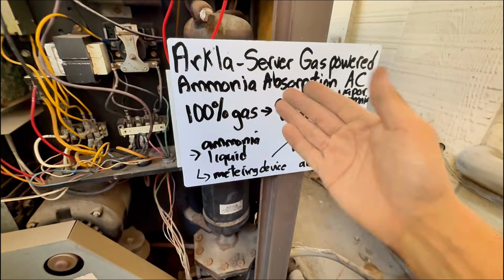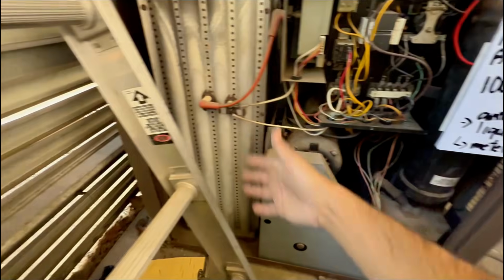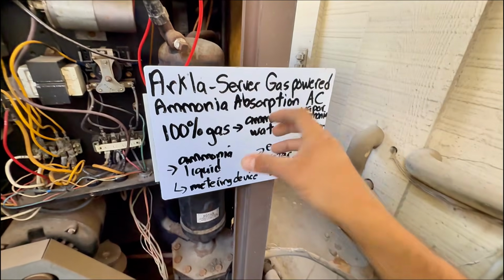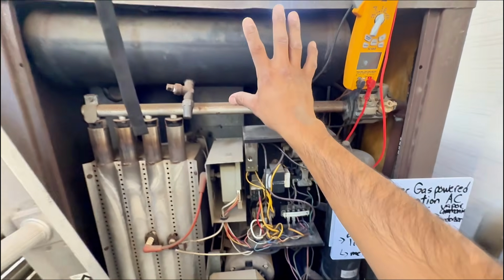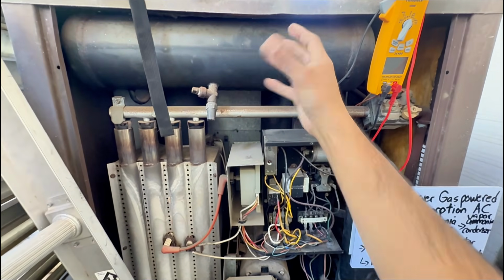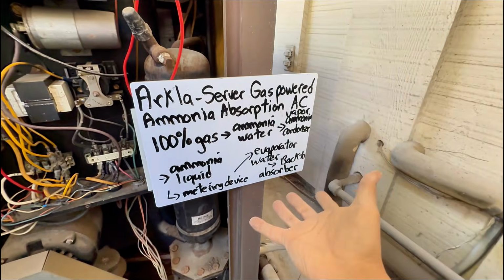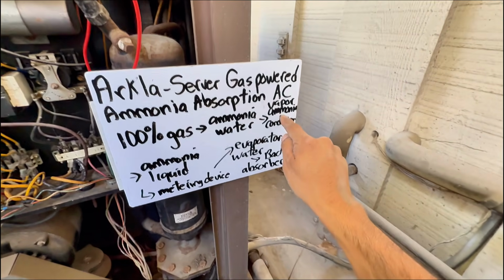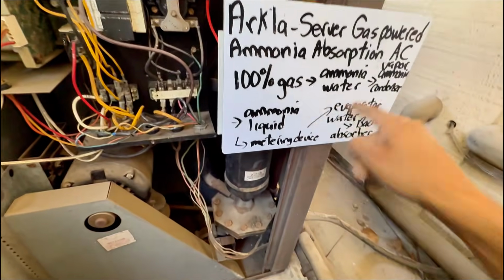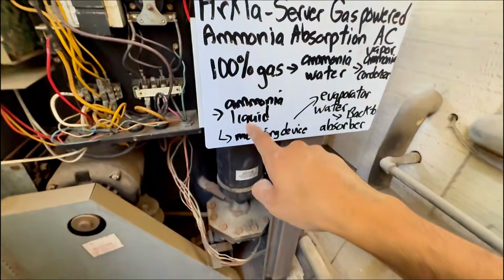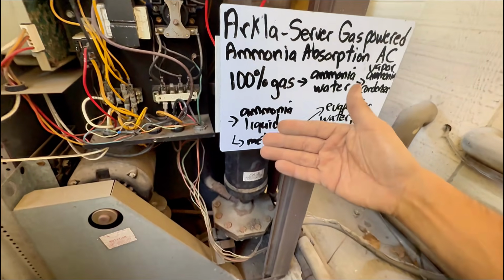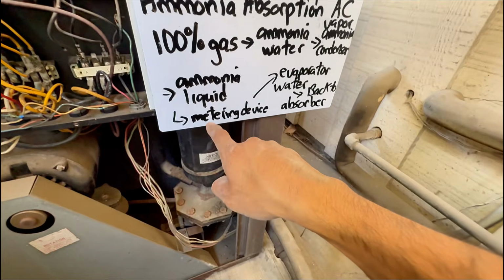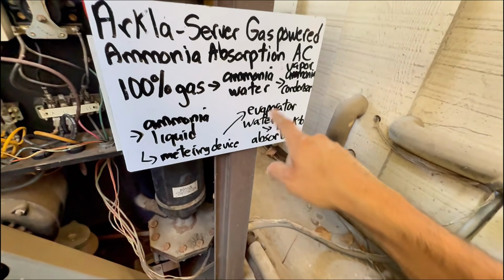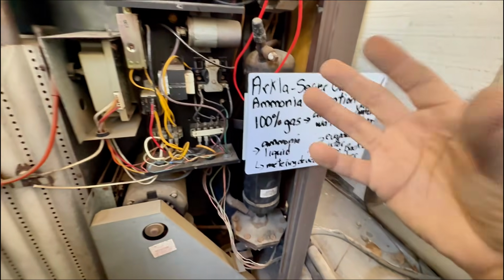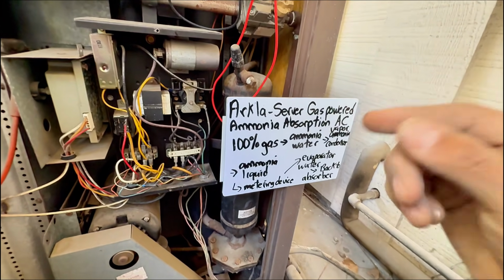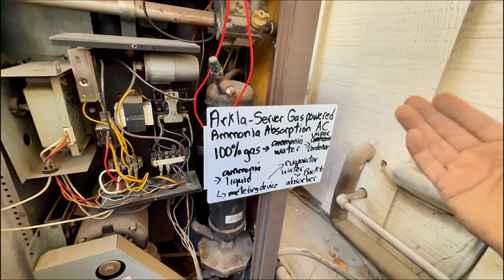But the way it does this is it uses gas, okay? It produces the burners, right? As you saw the flames, the burners. And the burners touch not directly the ammonia, but wherever the ammonia is encapsulated, and it drives the ammonia to separate from the water, and you have vapor ammonia then going to the condenser, and then it rejects the heat as you saw in the condenser fan. It comes out as liquid, right? Same thing as the refrigerant, your refrigeration cycle, and then it comes out to your metering device, drops the pressure, and in the evaporator, this is where it's a little bit different, and they usually call these indirect cooling. They don't call them DX cooling, they're indirect cooling.